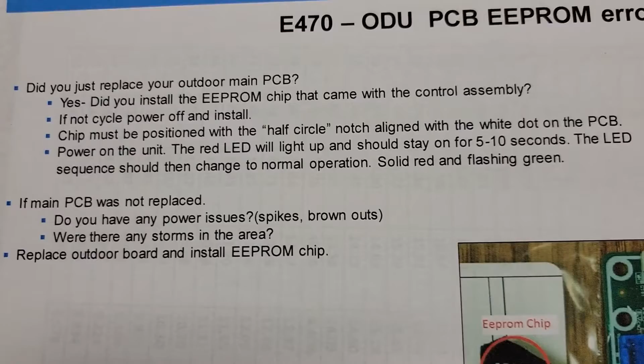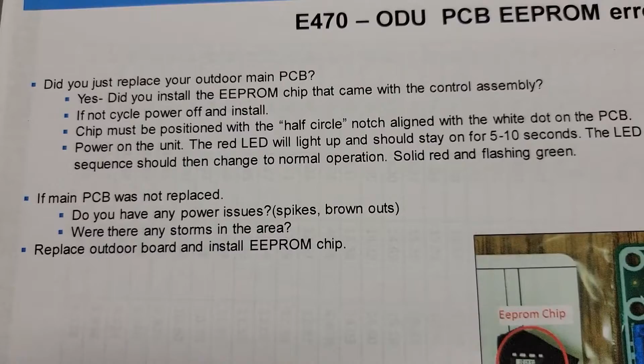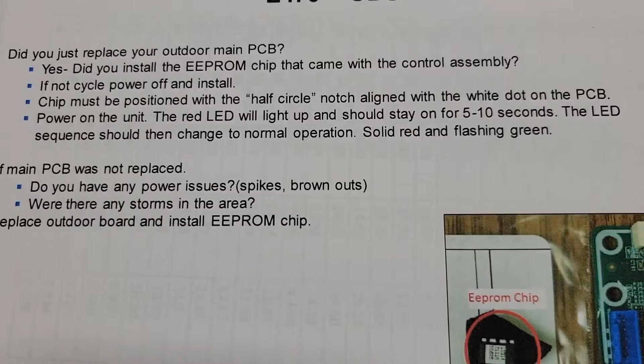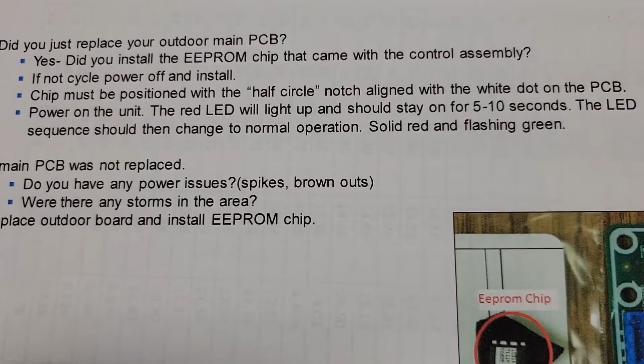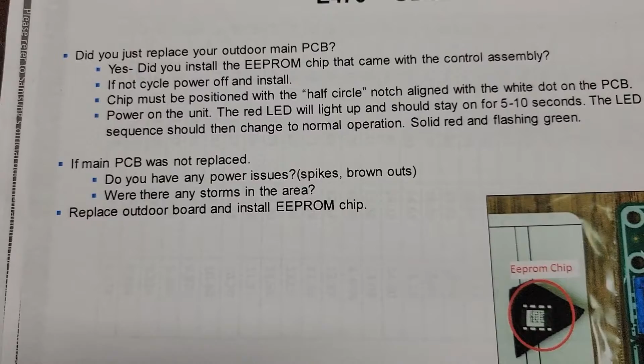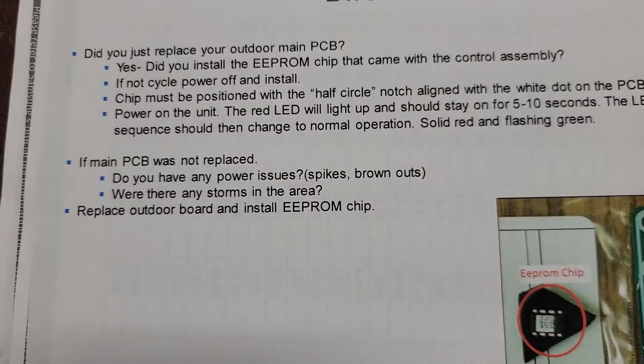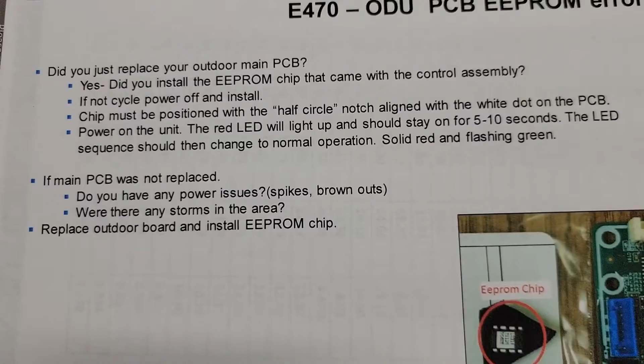Let's go over error code E470. Did you just replace your outdoor main PCB? Did you install the EEPROM chip that came with the control assembly? If not, cycle power off and install it. The chip must be positioned with the half circle notch aligned with the white dot on the PCB. Power on the unit. The red light will light up and should stay on for 5 to 10 seconds, then the LED sequence should change to normal operation: solid red and flashing green. If the main PCB was not replaced, check for power issues, spikes, brownouts, or storms in the area. Replace the outdoor board and install the EEPROM chip.